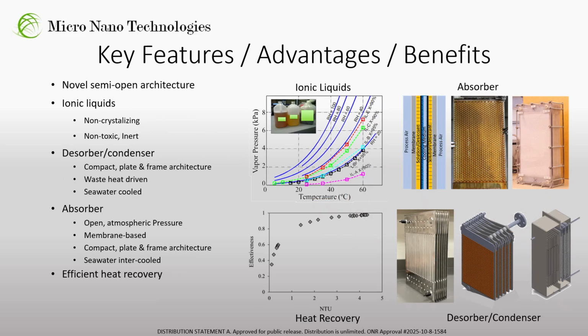The key features of MNT's technology are a novel semi-open architecture, a non-crystallizing, non-toxic ionic liquid desiccant, an integrated desorber condenser module, a membrane-based modular absorber, and the efficient recovery of heat to improve system efficiency. MNT's semi-open cycle provides an efficient, simple architecture operating at atmospheric pressure without the need for secondary scavenging or exhaust airflows. This simplifies the integration of this design within the ship.